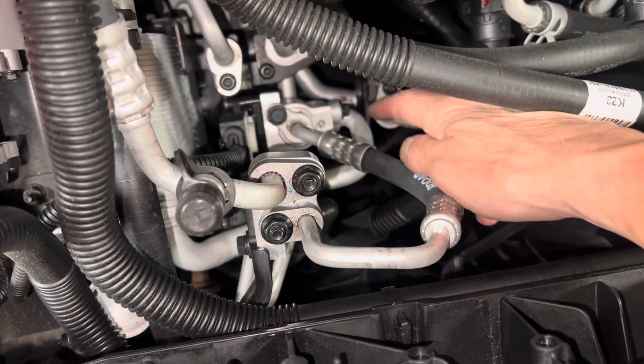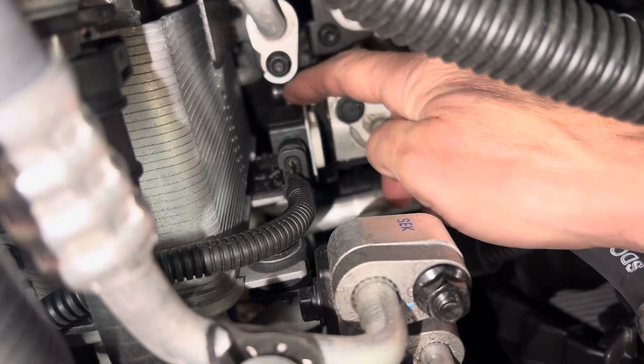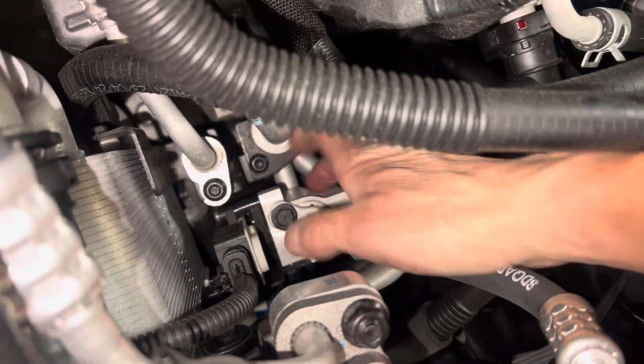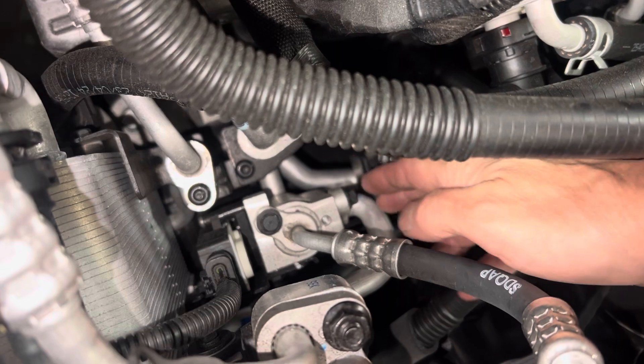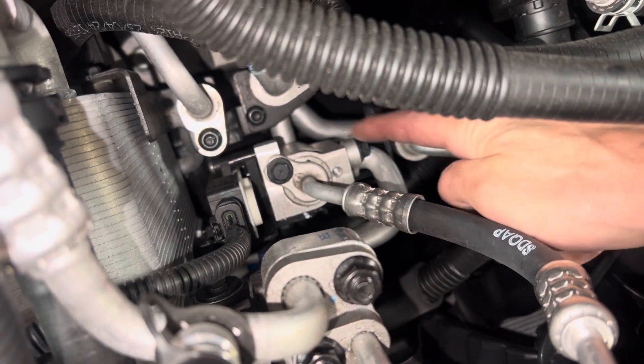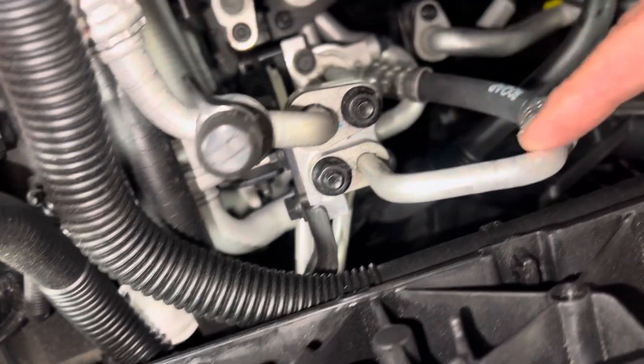I want to know more about this one. It's going to divert flow — if I'm not blowing smoke — and I'm looking for a center shaft from this device going through here, and it'll be rotating to change flow. So we've got three pipes, and by commanding this it will change the flow direction either here or down that pipe. This appears to be a liquid pipe — yes, it's a liquid pipe.